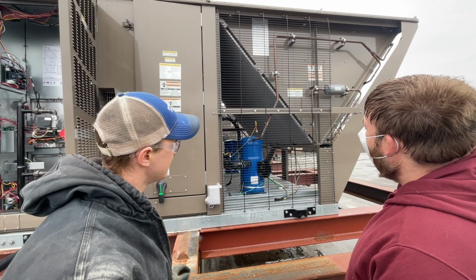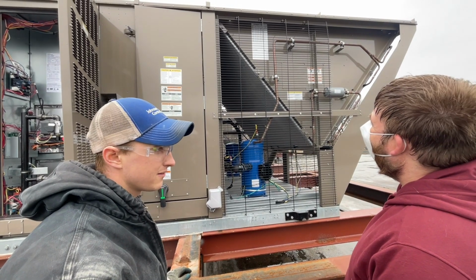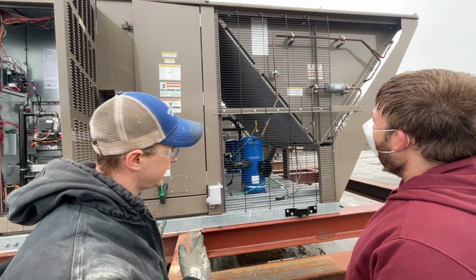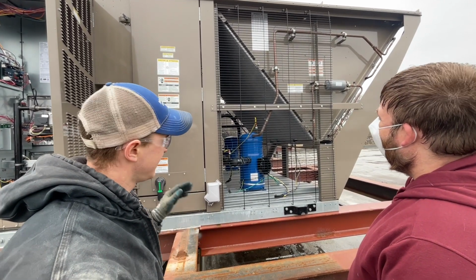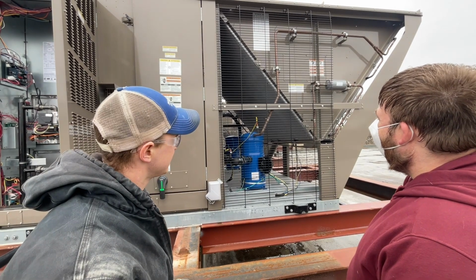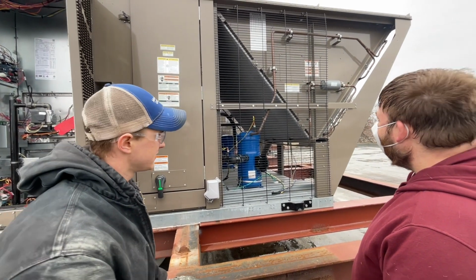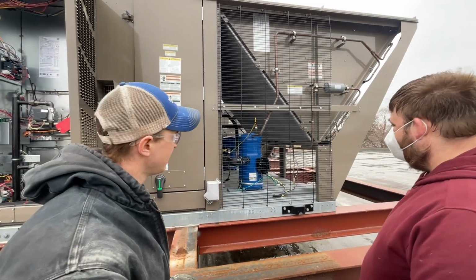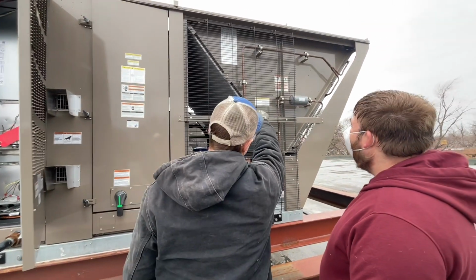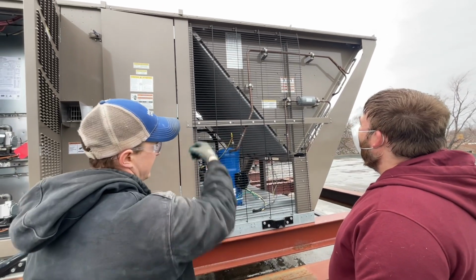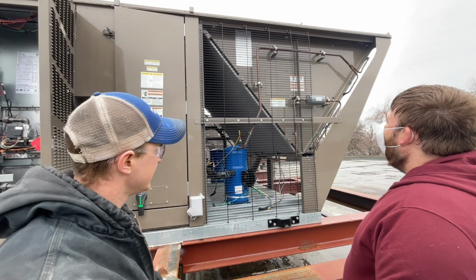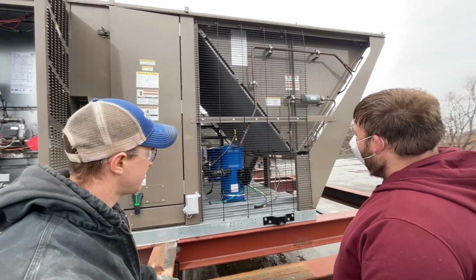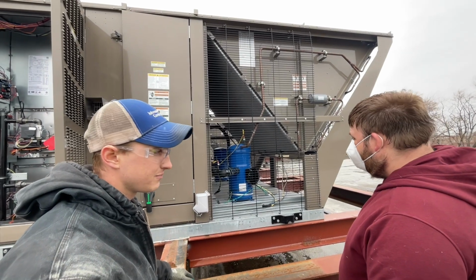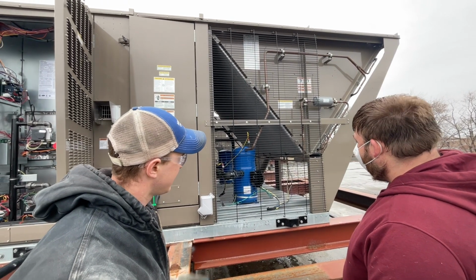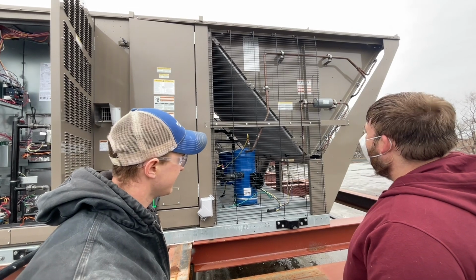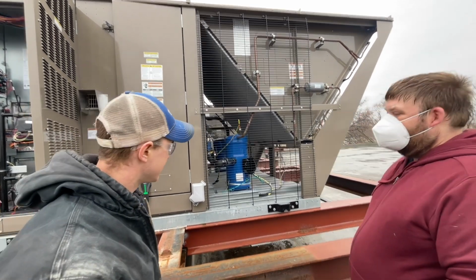You can use water, but definitely no chemicals whatsoever. No coil cleaner, no soap or anything, because it'll eat away at that little aluminum. Definitely no pressure washer. So just high volume, low pressure water if you're doing anything. And there's little covers you can see with those 4 screws. You can take those off and hit it from the inside, but definitely very low pressure. Just get a volume of water going through there and that cleans it. But honestly, most of the time you just need a very soft bristle brush to knock it off. They tend to stay a lot cleaner and it doesn't pack in the coils like the old ones did.